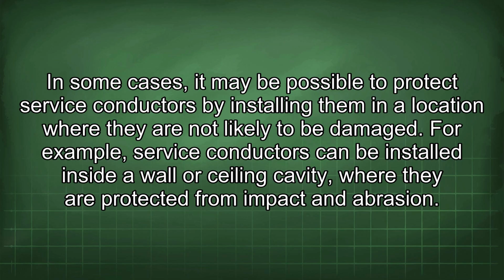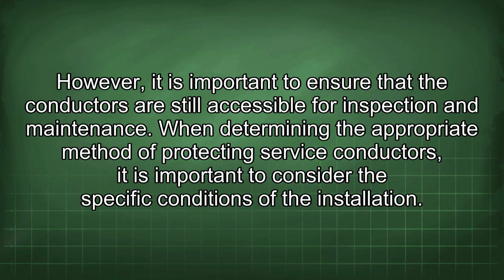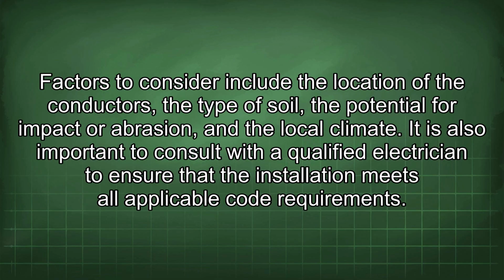In some cases, it may be possible to protect service conductors by installing them in a location where they are not likely to be damaged. For example, service conductors can be installed inside a wall or ceiling cavity where they are protected from impact and abrasion. However, it is important to ensure that the conductors are still accessible for inspection and maintenance. When determining the appropriate method of protecting service conductors, it is important to consider the specific conditions of the installation. Factors to consider include the location of the conductors, the type of soil, the potential for impact or abrasion, and the local climate. It is also important to consult with a qualified electrician to ensure that the installation meets all applicable code requirements.